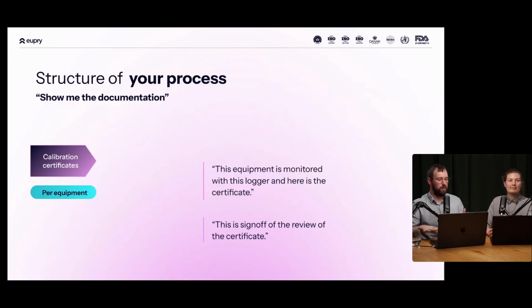What's really important to take away is that you understand this logical order rather than going directly to the calibration certificate. How can you evaluate what's in there? How can you sign off a calibration certificate if you don't know where those requirements come from? And how do you know what those requirements should be if you don't have your process and product knowledge? There's a lot of value in understanding the choices made and the baseline for this. If you can show the auditor that this is the approach you took, that you didn't start by just getting a certificate and working your way back up to the requirements, but actually took that logical order, that was the decision. So you're not fitting the 2 to 8 degrees into a calibration certificate that covers minus 20 to 50.